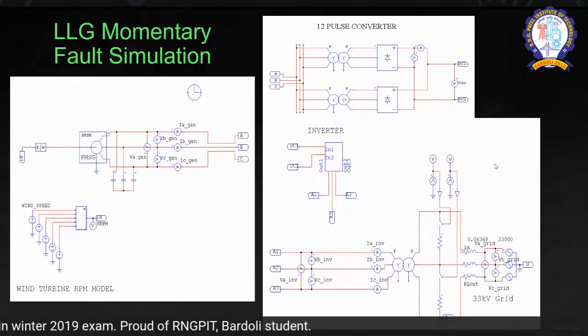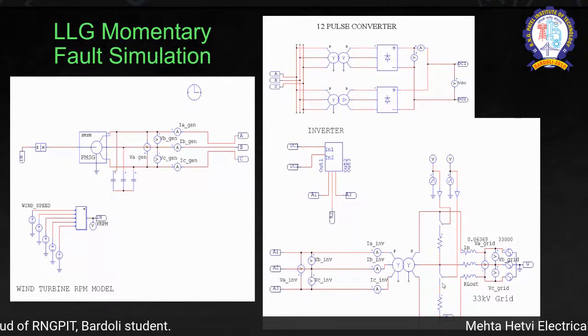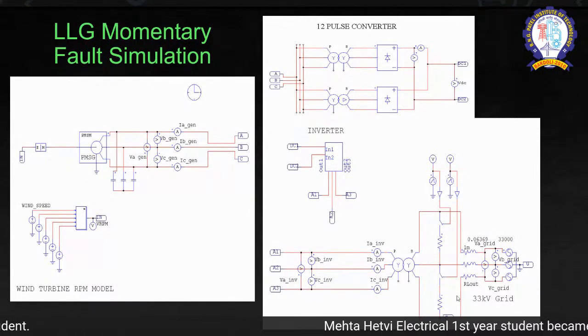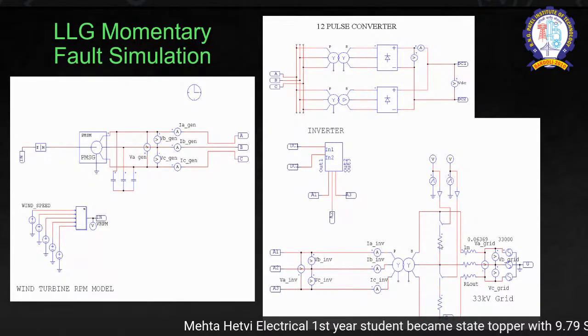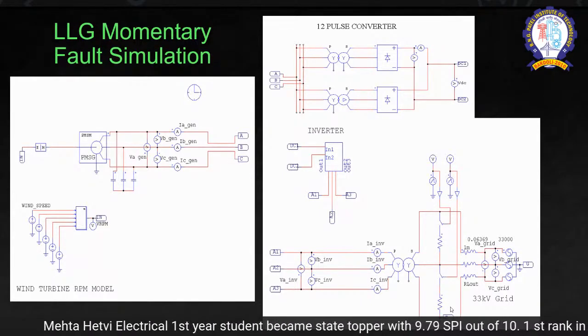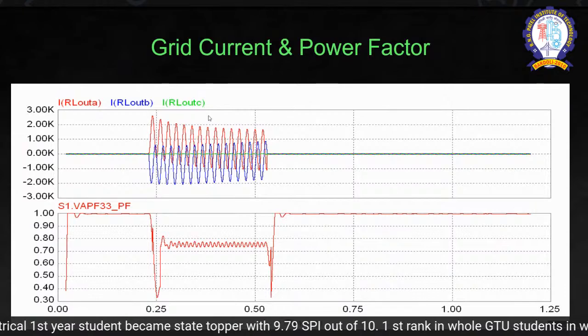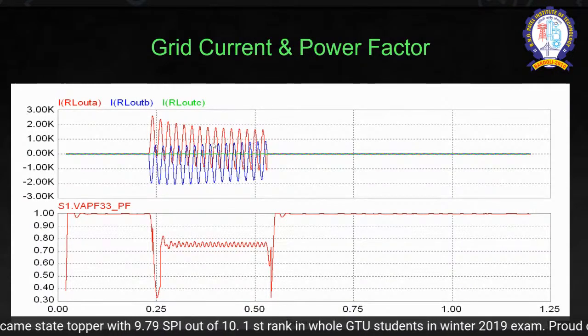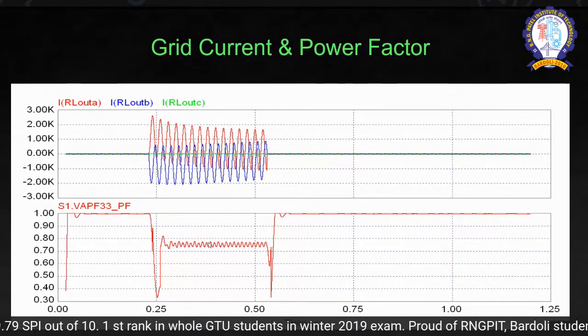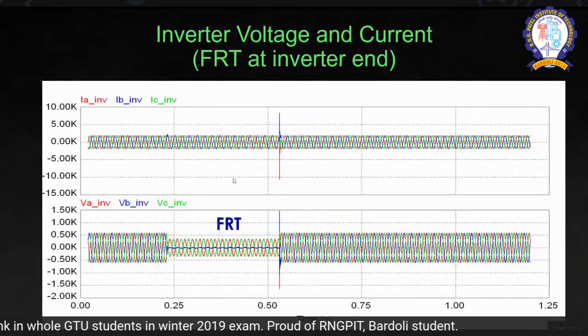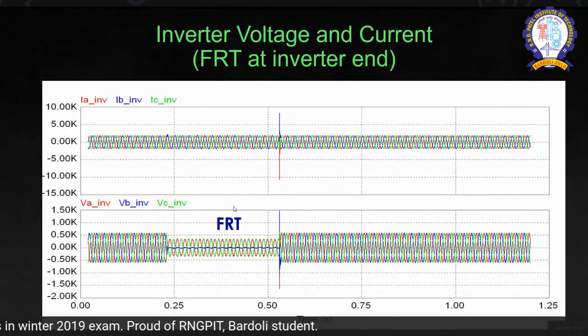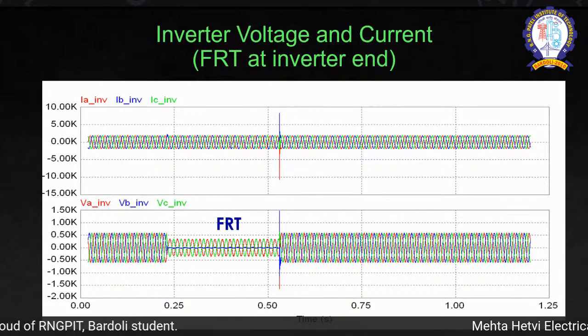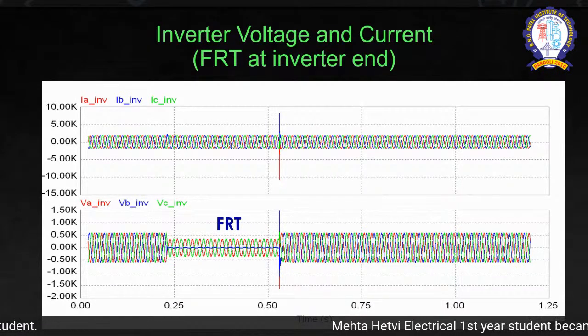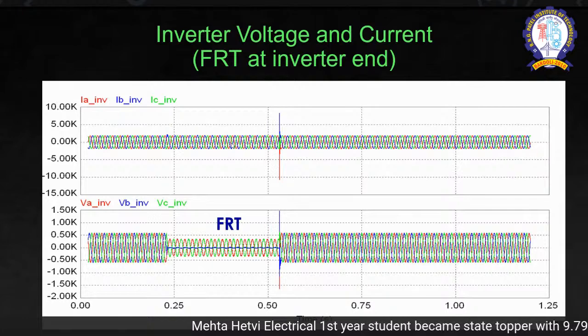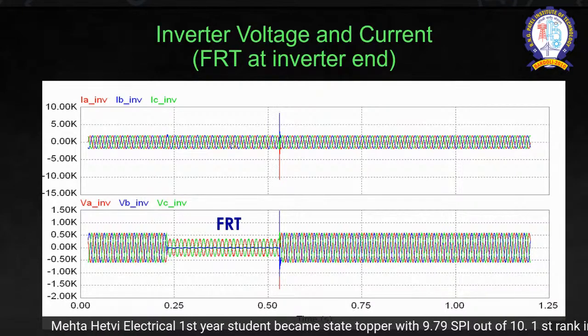So now in this case, if there is a double LG fault over here from the grid side, line to line fault and line to ground fault, then this is the increment in the grid current and decrement in the power factor. This effect is known as FRT. However, the grid connection is tightly connected, so there is no collapse in the current, there is a collapse in the voltage, known as the FRT.